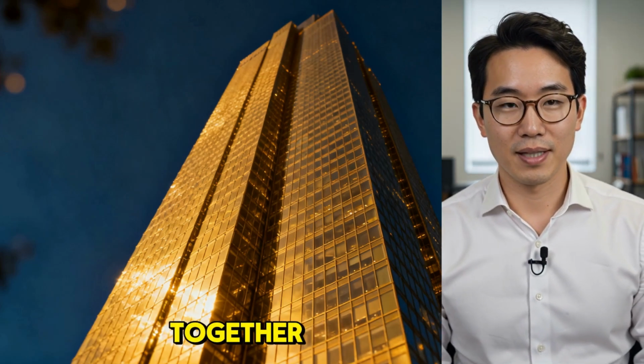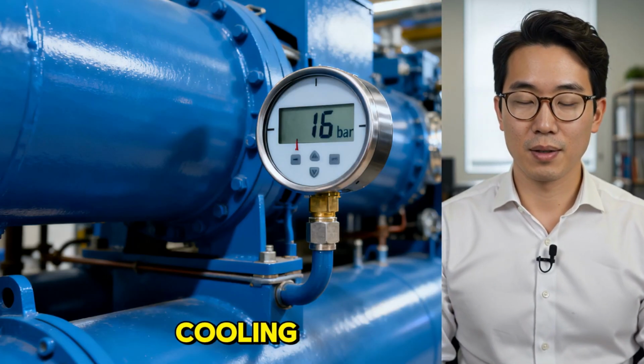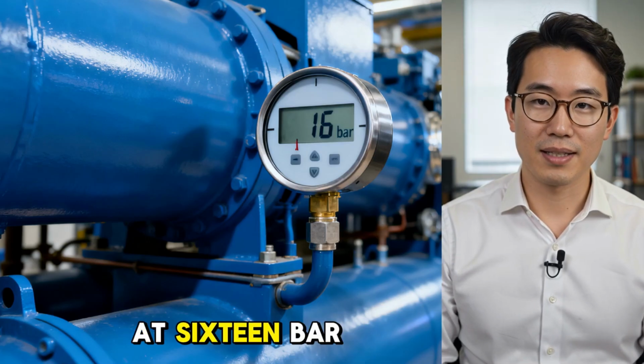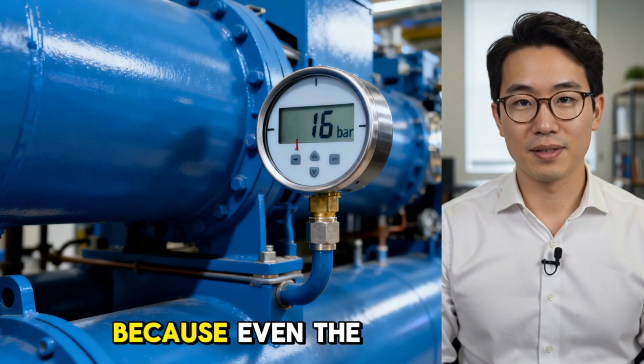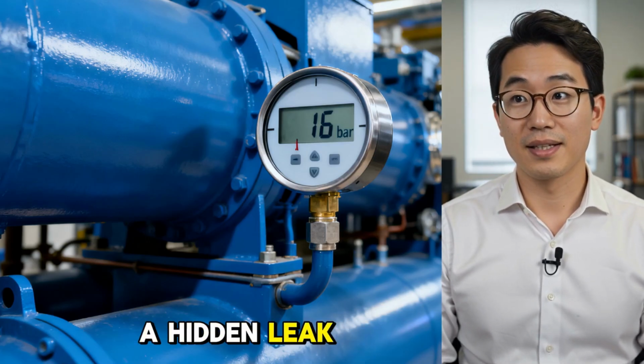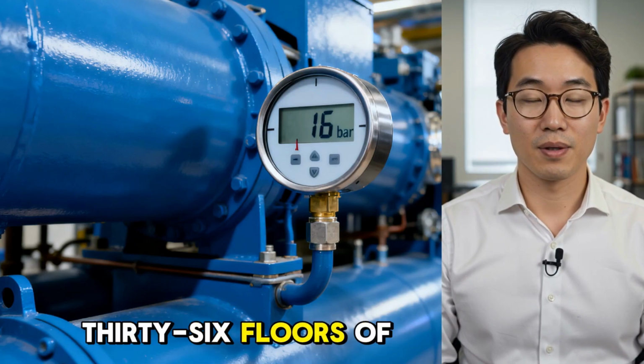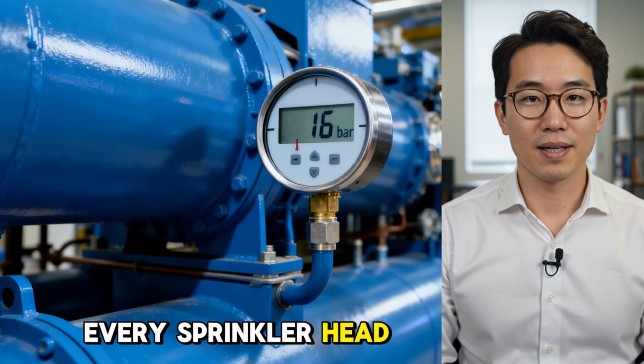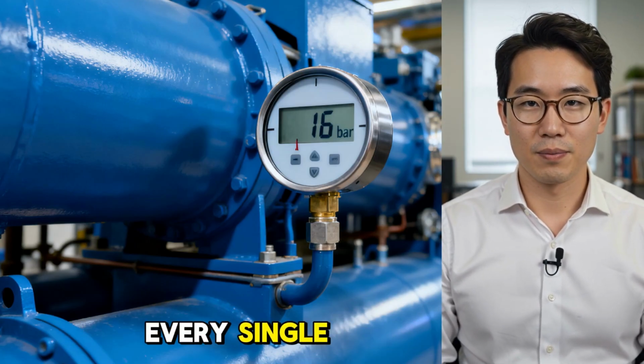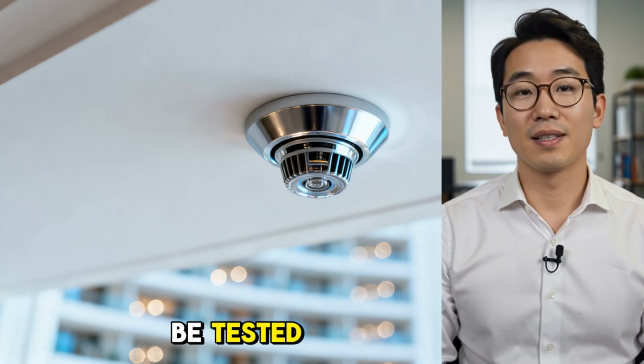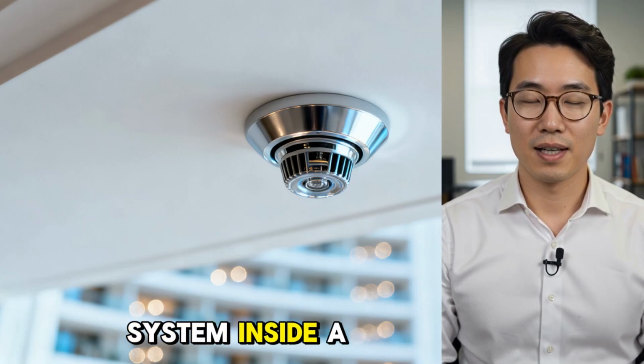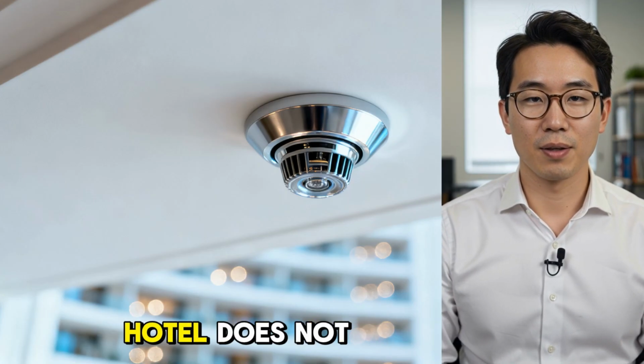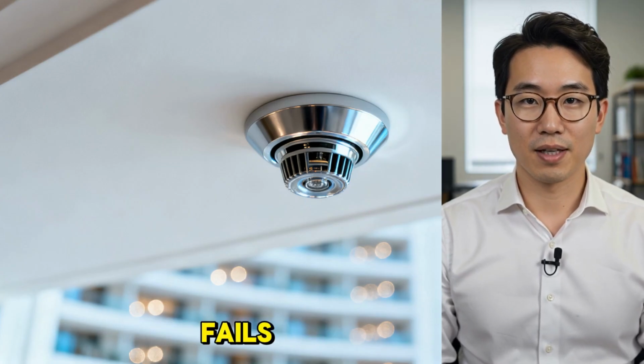4 industrial chillers together, capable of 8,000 tons of cooling, had to be pressure tested at 16 bar for a full hour, because even the smallest pressure drop meant a hidden leak somewhere buried inside 36 floors of ductwork. Every sprinkler head, every fire alarm, every single one across every single floor had to be tested, because a fire suppression system inside a 211-meter hotel does not get a second chance if it fails.